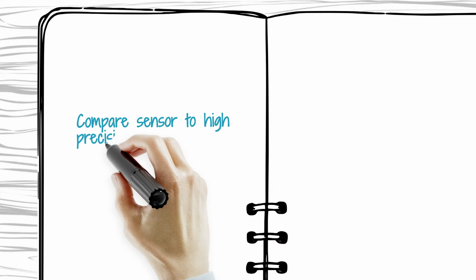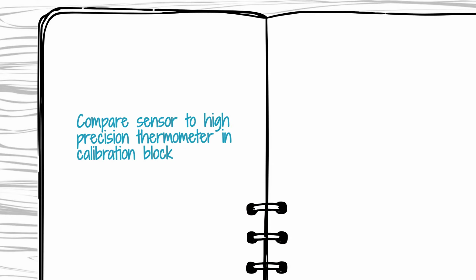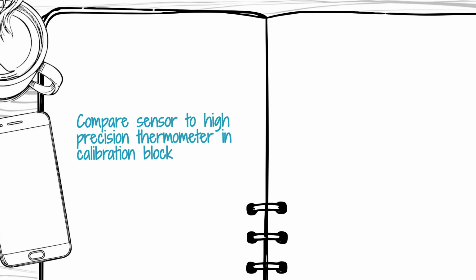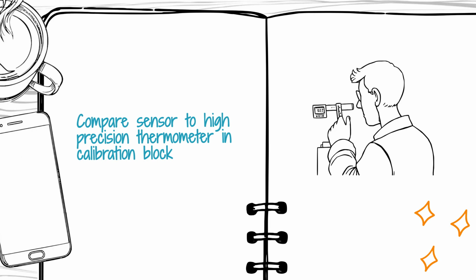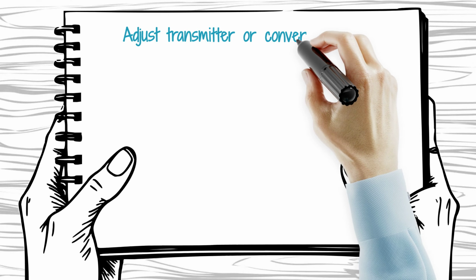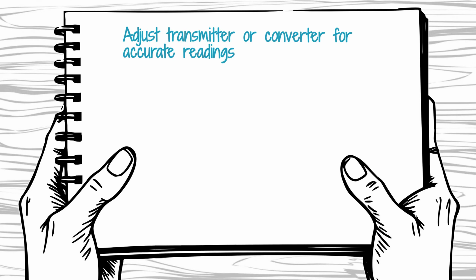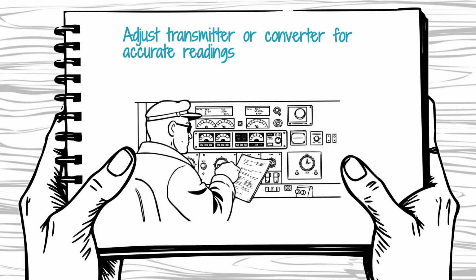Place the ship's sensor alongside a high-precision reference thermometer into the calibration block. Start the process at the lower end of the expected operating range, allowing the temperature to stabilize completely before comparing the two readings. If the control room display or local indicator shows a deviation, you must adjust the transmitter or the signal converter. For digital systems, this involves adjusting the 0 and span settings to align the output signal, typically 4 to 20 milliamps, with the actual measured temperature.